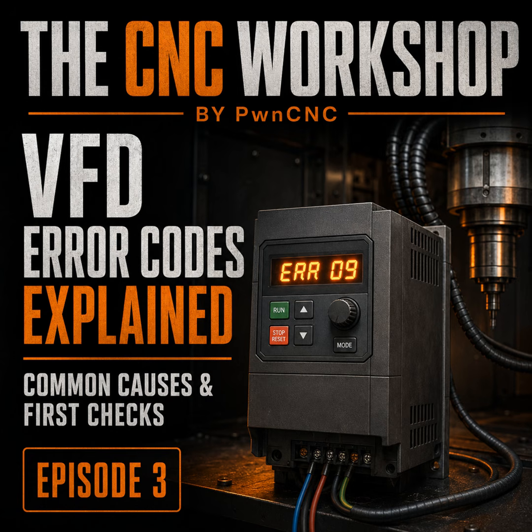That is a beautifully annoying troubleshooting result. It is, because the cable can look fine from the outside. A cable may technically fit inside a drag chain and still be routed badly. If the chain is crowded with spindle power, coolant tubing, control wires, and air lines, the cable can be crushed or forced into a bend it was never designed to make.